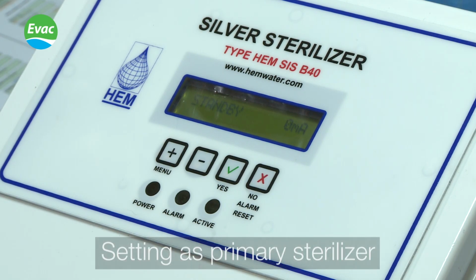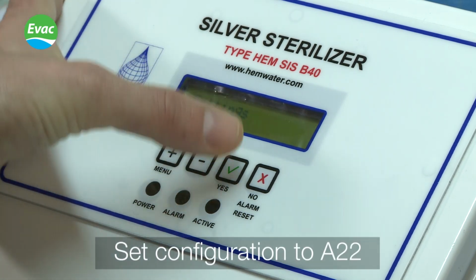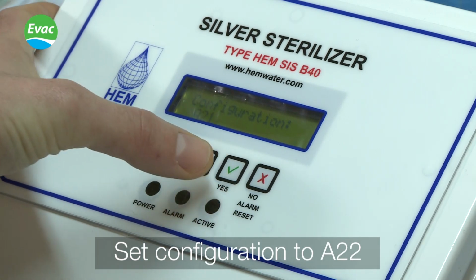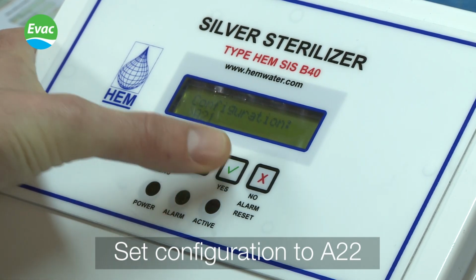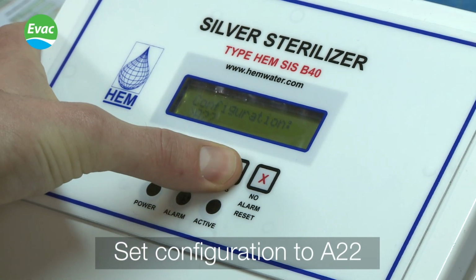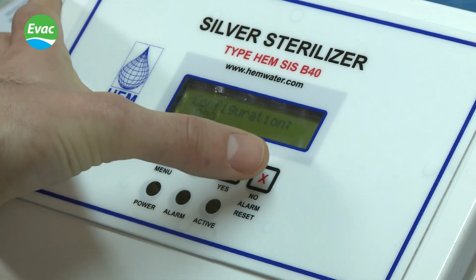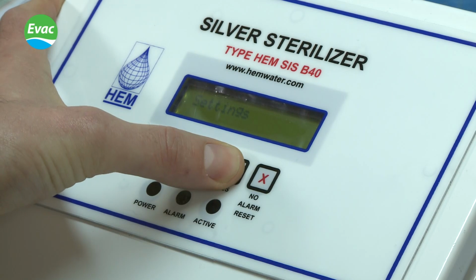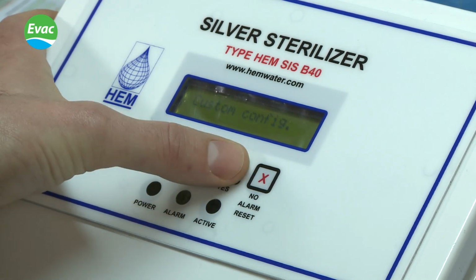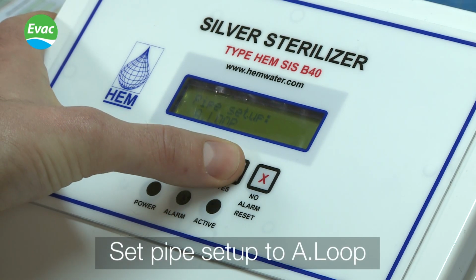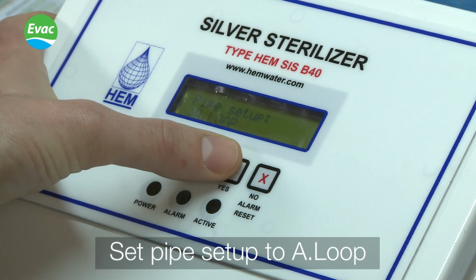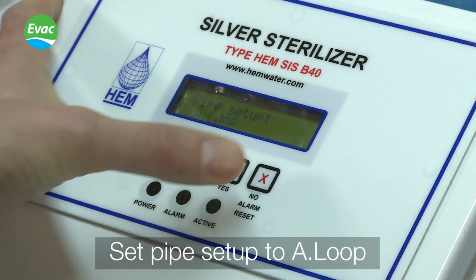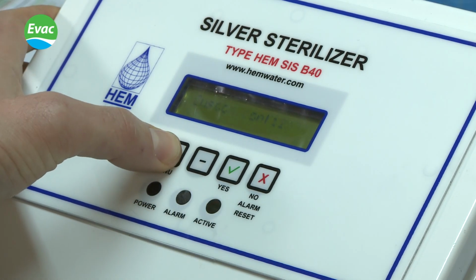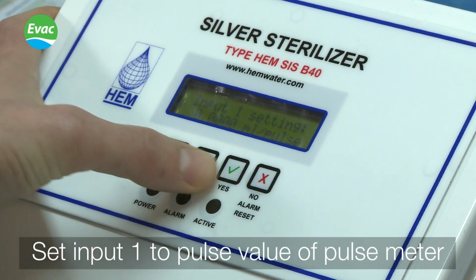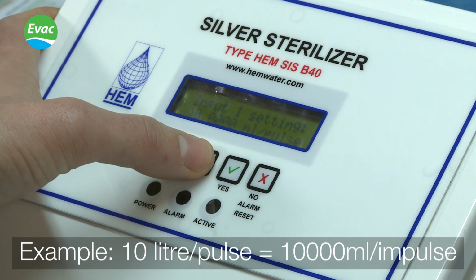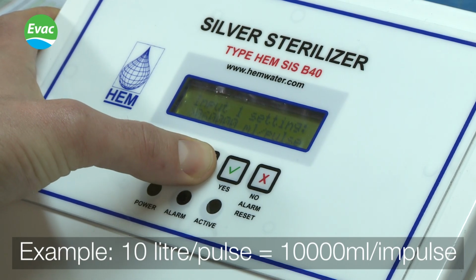Setting as primary sterilizer. In settings, set configuration to A22. Set pipe setup to A.Loop. Set input 1 to the pulse value of your pulse meter. Example, set 10 liters per pulse, equal 10,000 milliliters per impulse.